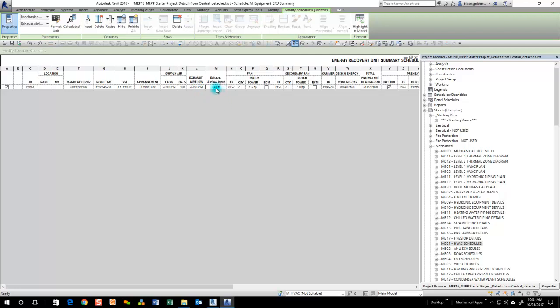So you could obviously override an input, which I have unhidden right now. An input, as we've discussed in many different chapters in this user manual, is essentially an override. So if you needed to override a given value from connected airflow, you could edit the input and then the scheduled value would update. And when you were done, you could hide that column. So that's one method to do it. However, we wanted a schedule already set up where users could just go to if they need to override values.